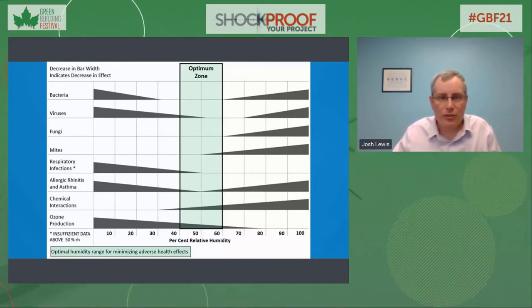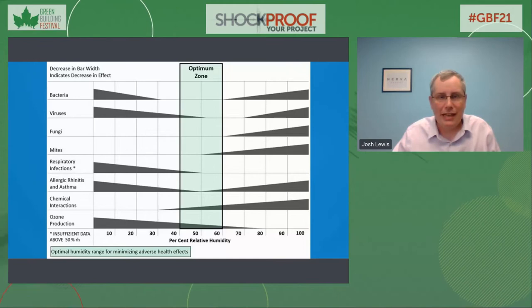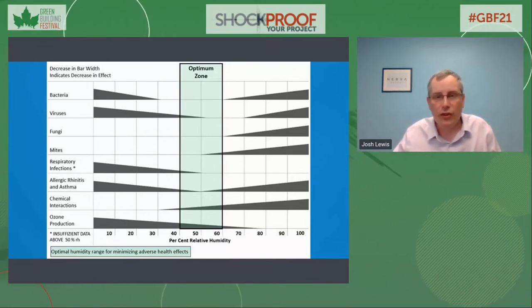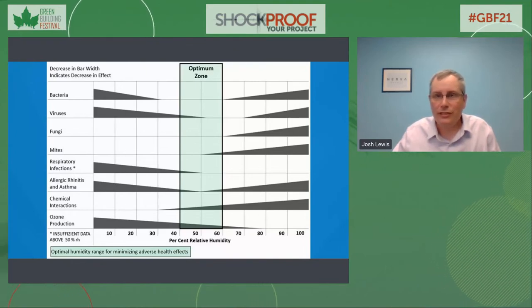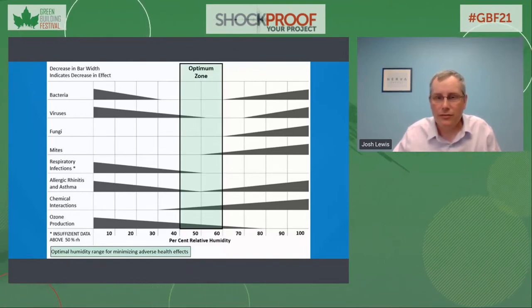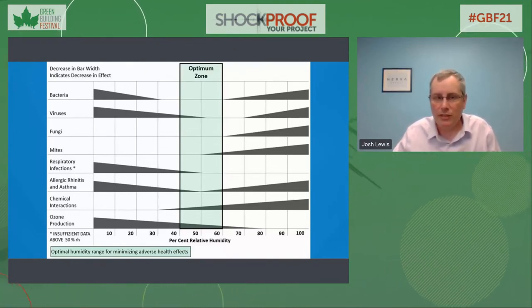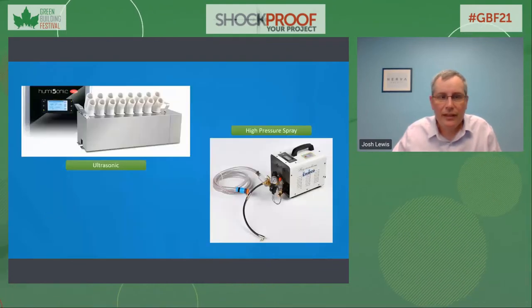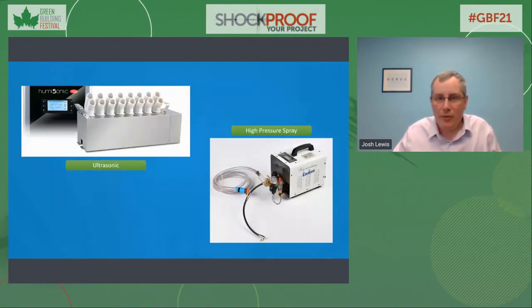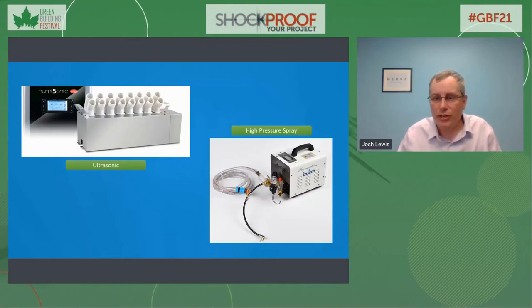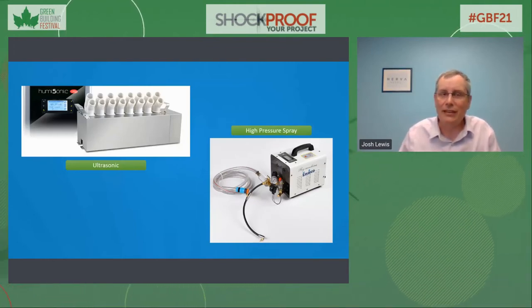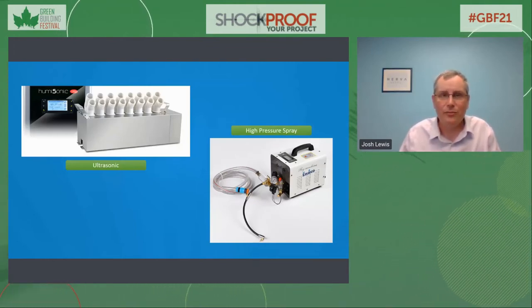But that is a direct result of the building doing what it was designed to do, bringing in large volumes of makeup air from outdoors, heating it up to 21 degrees Celsius and dumping it into the hallways. No other result should be expected at that point. The solution to wintertime humidity issues is pretty straightforward, but it does have a penalty in terms of cost and energy.